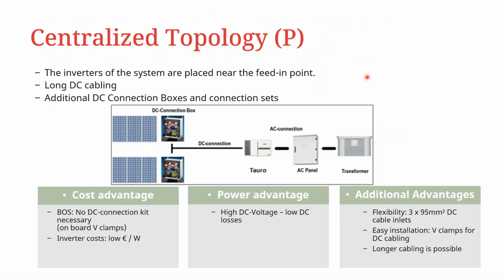For the centralized topology, you have the possibility to use, like we said, thicker cables on the DC side. In terms of the cost advantage, the DC connector kit is not necessary, because like for the snap inverters, we said that when you use the centralized design, you do need the DC connector kit. But for the Tauro inverter, the V clamps are already integrated into the inverter. Therefore, the inverter costs are quite low if you look at the unit cost per watt.